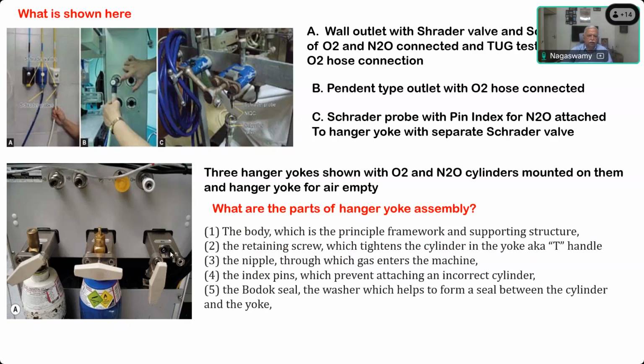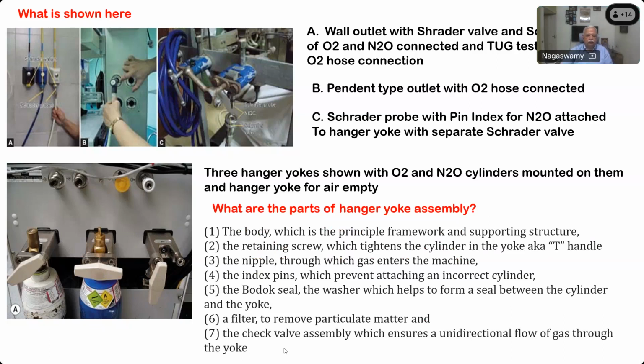There is a Bodok seal, the washer which helps to form a seal between the cylinder and yoke, and a filter to remove particulate matter. This is inside here. Okay, so these are all the components. And the seventh one is a check valve assembly which ensures a unidirectional flow of gases through the yoke.